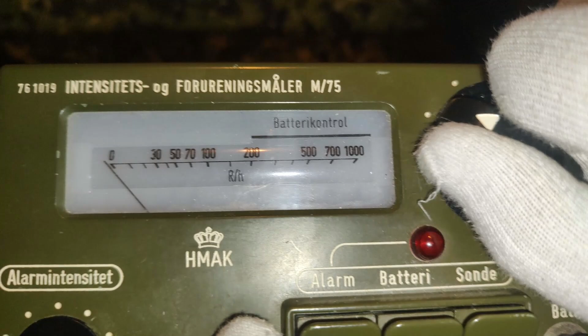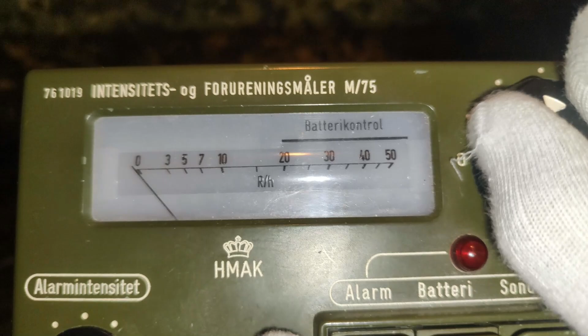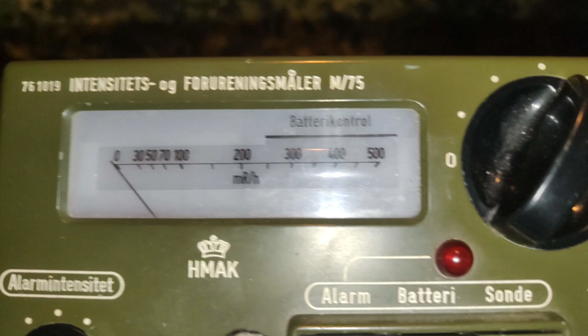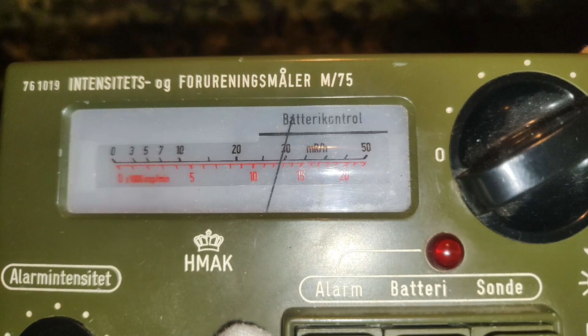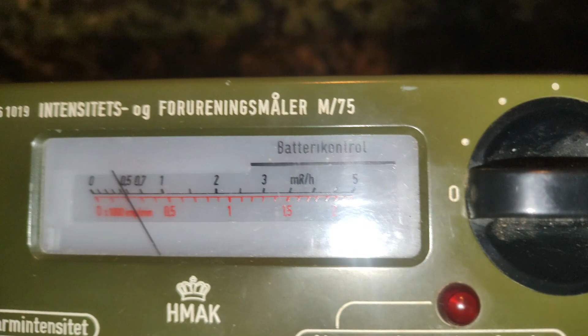Now the ranges are 0 to 1000 Röntgens per hour, so 10 sieverts per hour. Then 0 to 50 Röntgen per hour, or 0 to 500 millisieverts per hour. Here we have 0 to 5 Röntgen, and 0 to 500 milliröntgen, so 5 millisieverts, and 0 to 50 milliröntgen per hour, and 0 to 5 milliröntgen per hour. The bottom red line is counts per minute times 1000, going up to 20,000 counts per minute.